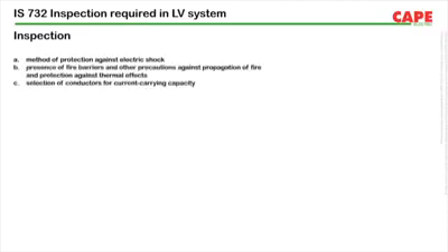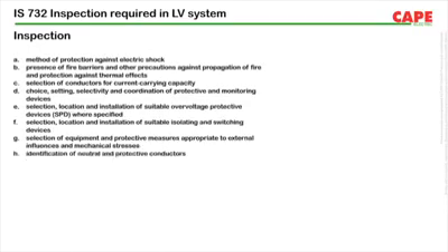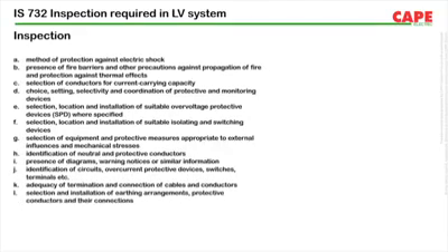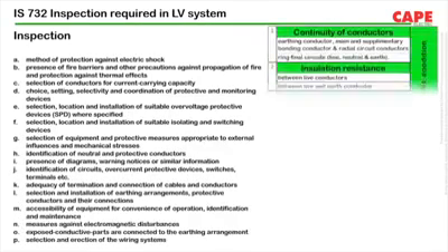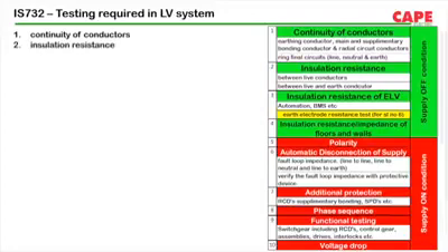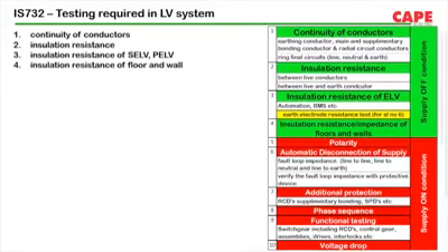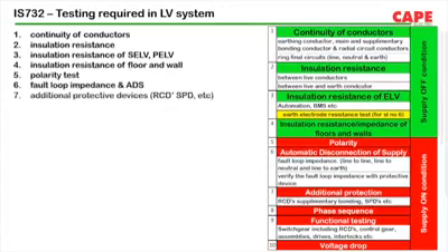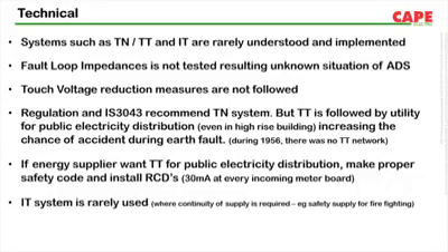The new IS 732 published in February 2019 is of high importance at this stage. Industries and commercial buildings who conduct inspection and testing as per the new IS 732 can achieve a high degree of safety. Few important points from my presentation again. Systems such as TN, TT and IT are rarely understood and implemented. Fault loop impedance is not tested, resulting in a kind of non-awareness or no information of the condition of automatic disconnection of supply.